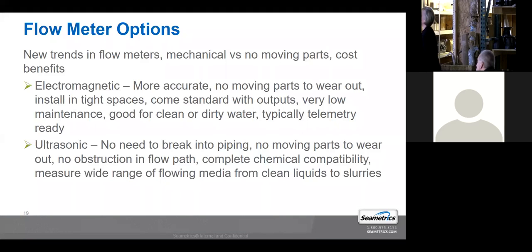We did bring an ultrasonic meter here. Doesn't look like a meter at all, but this is actually a meter. These are the electrodes. It sets on a pipe, and these straps are so long because it works on up to 20-inch pipe. 2 to 20-inch pipe. This one's meant to be a portable verification tool. This isn't meant to mount in line permanently. This is a portable verification tool meter. But this is an example of an ultrasonic meter.